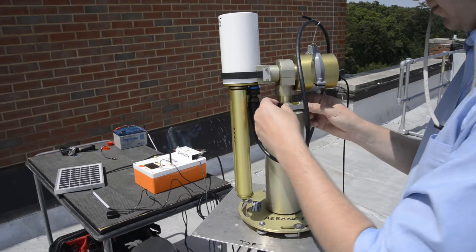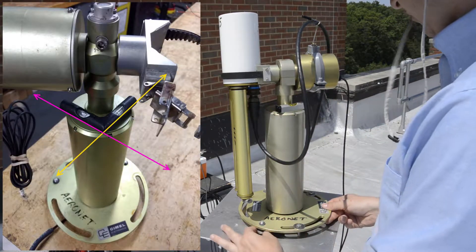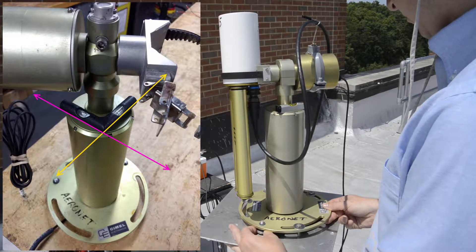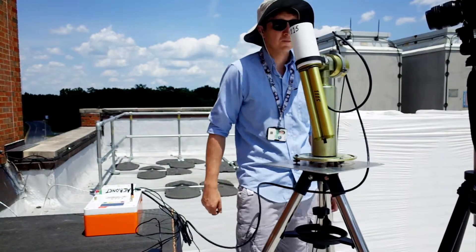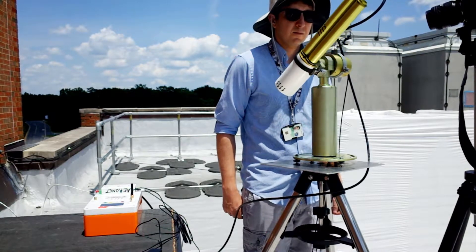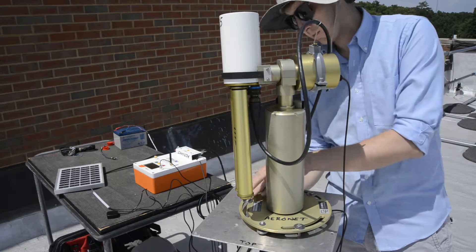There are two leveling screws on the robot base. Use the bubble level and the two screws to level the robot. Once the robot is level, check the sunspot alignment again, and then tighten the three bolts.